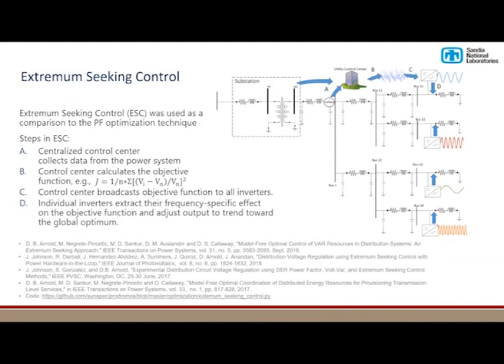And so volt-VAR is pretty straightforward. We understand what that is. Based on the local grid voltage, we inject or absorb reactive power at the device. The two other probably less well-known capabilities are extremum seeking control, which is depicted here, and the optimization, which I'll talk about on the next slide. In this one, shown on the right, we have a few different inverters that are all injecting a probing signal that's a reactive power ripple.